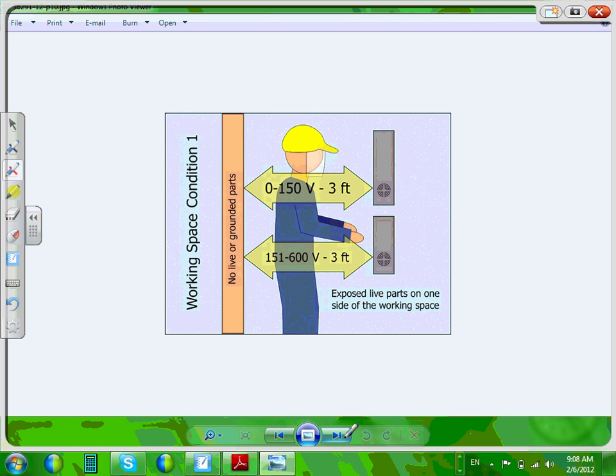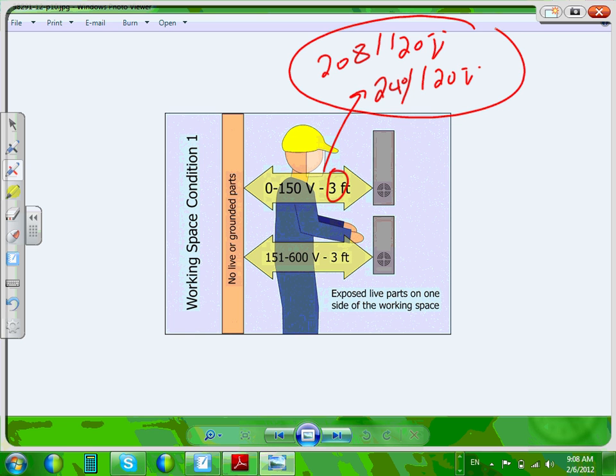If I have no live parts, here's my panel, no live parts. This is 150 volt to ground. You need 3 feet or less. So this will cover your 208 system, 120 volt, 240/120 volt, right, to ground. Then you need a 3. So if your panel right here is any of these 2 systems, you are 3 feet, and in front of you, no live or grounded parts. In front of you is what we call condition 1. Any question, guys, about condition 1? Piece of cake, 3 feet.